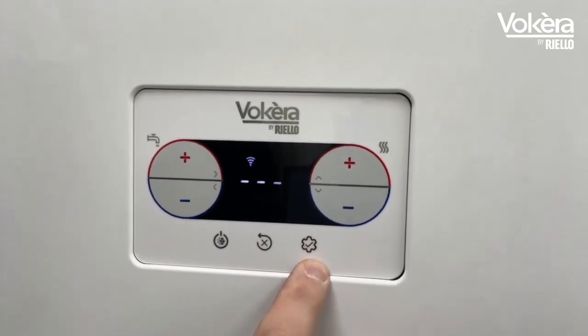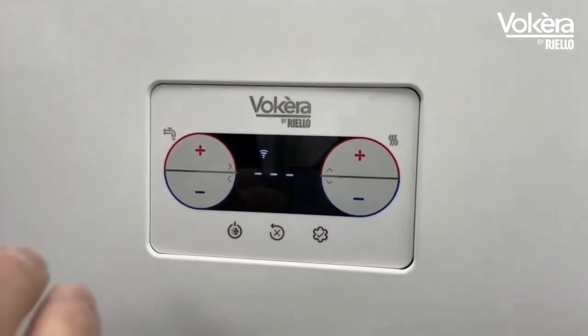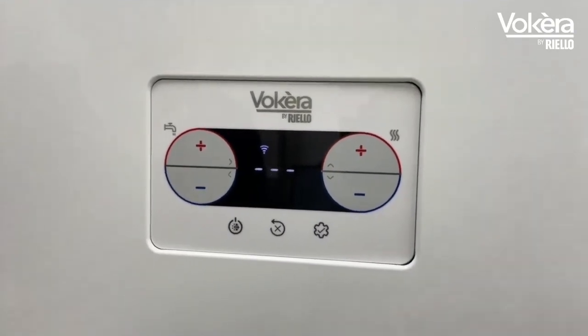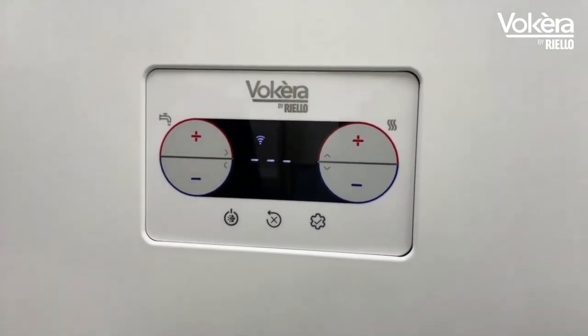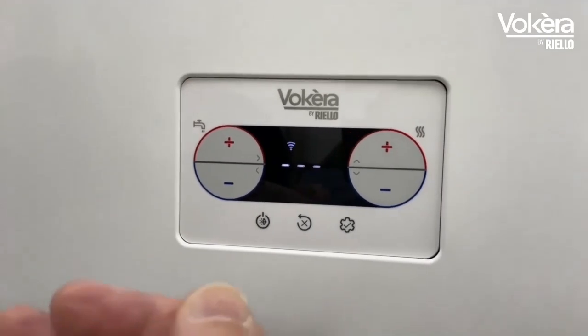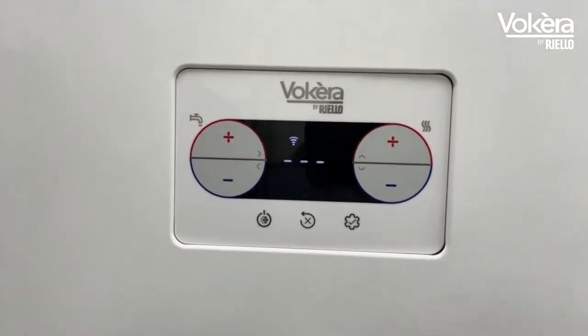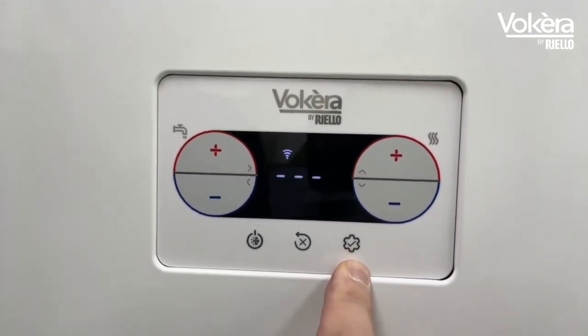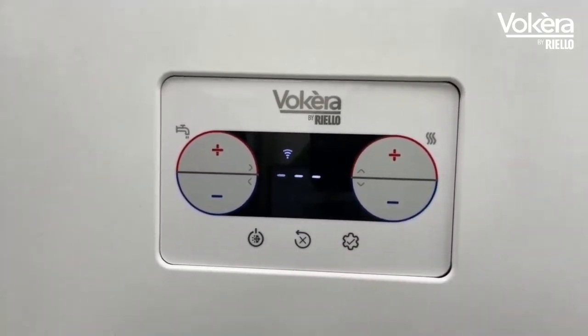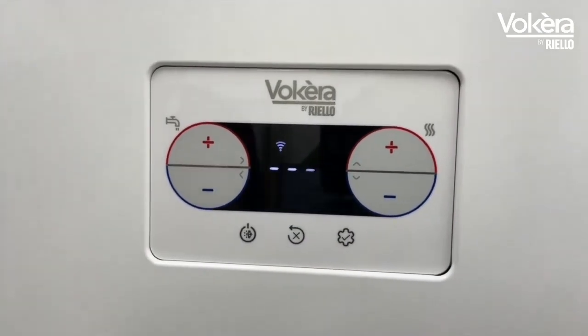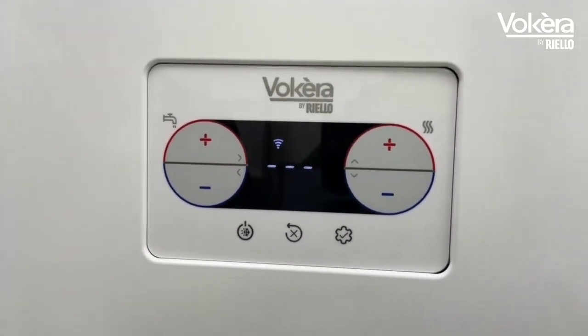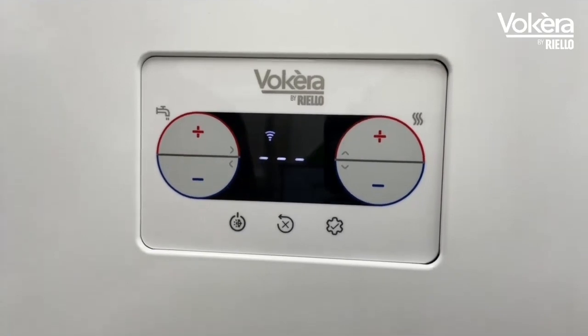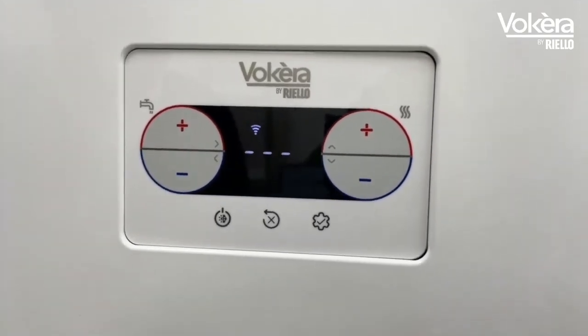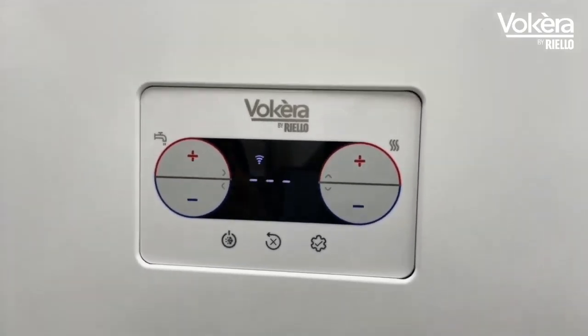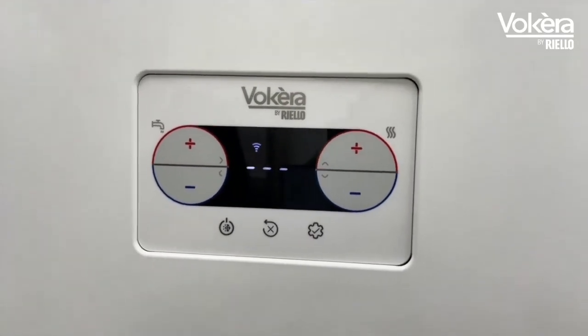A press and hold for 2 seconds will enable you to change some of the boiler user parameters. Not many, but there's no password protection on the user parameters. A second 2-second hold press on that button will request a password. Then we can range rate the boiler. We can enable weather compensation. We can enable OpenTherm. We can change the boiler performance quite markedly.